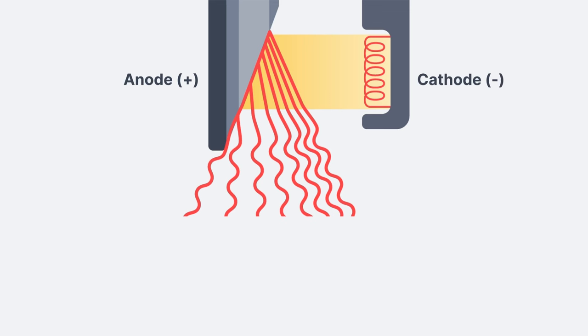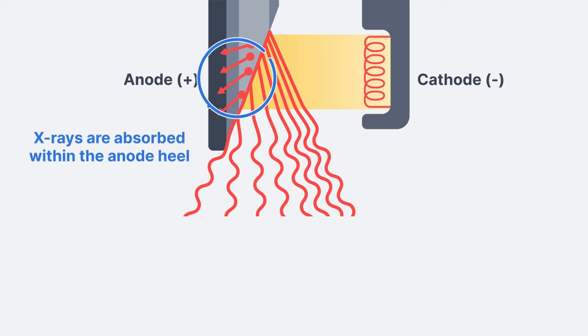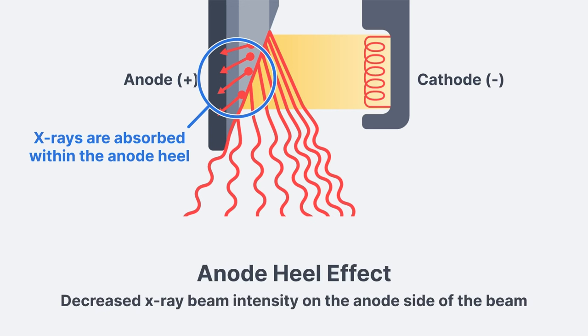So why does this actually happen? X-ray photons are created throughout the anode and not just on the surface. Some of the photons get created deep in the anode and then they get absorbed within the anode heel. As a result, the x-ray beam has fewer photons on the anode side compared to the cathode side. And that's really the definition of the anode heel effect: decreased x-ray beam intensity on the anode side of the beam.